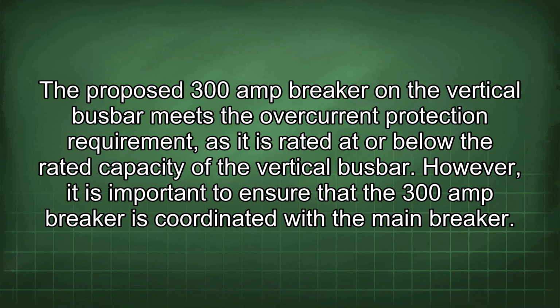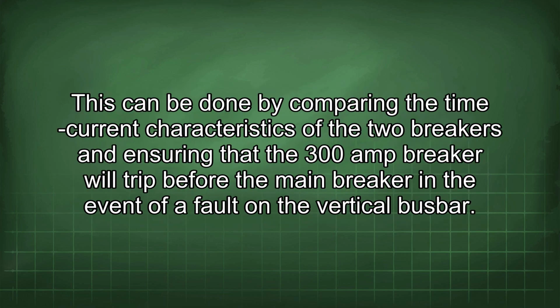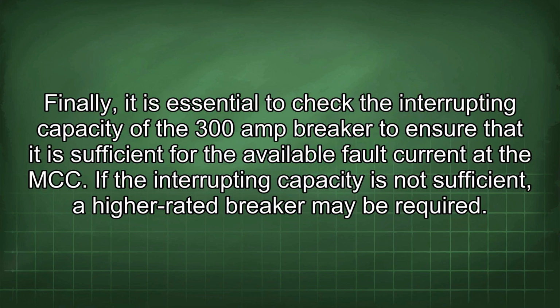However, it is important to ensure that the 300 amp breaker is coordinated with the main breaker. This can be done by comparing the time current characteristics of the two breakers and ensuring that the 300 amp breaker will trip before the main breaker in the event of a fault on the vertical busbar. Finally, it is essential to check the interrupting capacity of the 300 amp breaker to ensure that it is sufficient for the available fault current at the MCC. If the interrupting capacity is not sufficient, a higher rated breaker may be required.